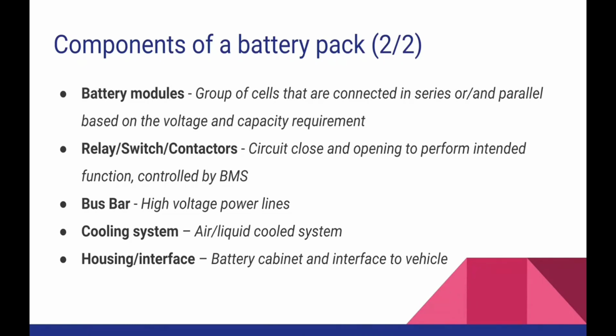So in order to achieve that, we want a cooling system. The cooling system can be either air-cooled or liquid-cooled, based on the application and capacity of the battery pack. For a 48 volt system, an air-cooled battery pack would be sufficient, whereas for a 380 volt, 600 volt, or even 900 volt system, we may need a cooling system more efficient than air-cooled, so we prefer a liquid-cooled system.